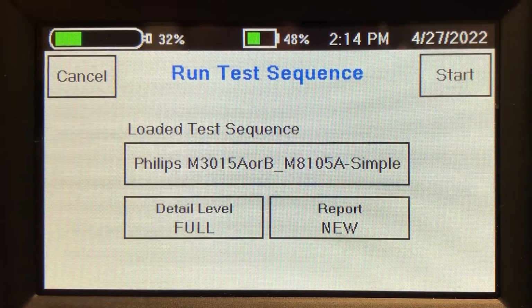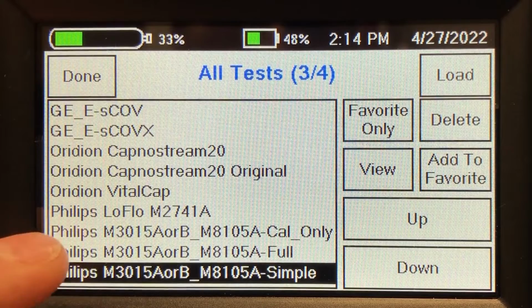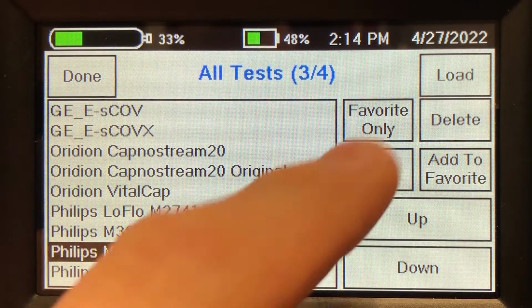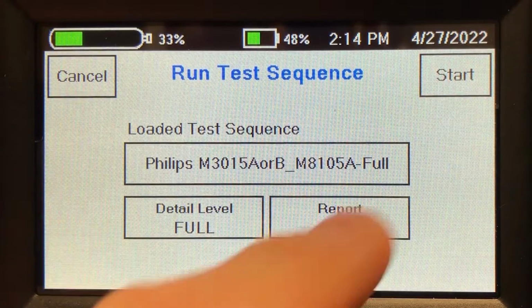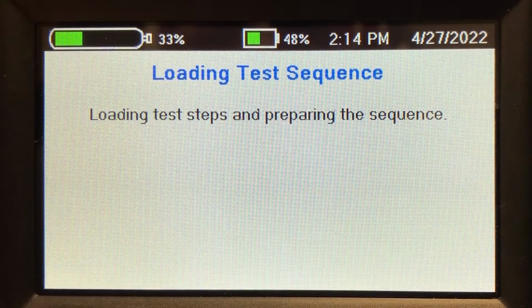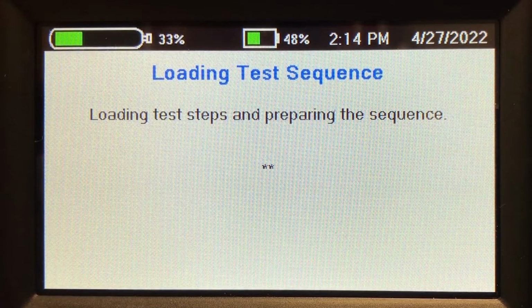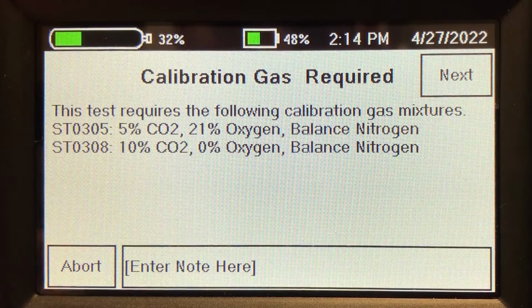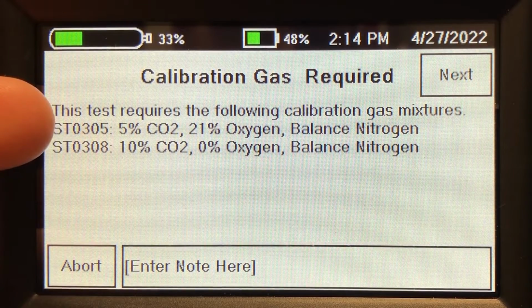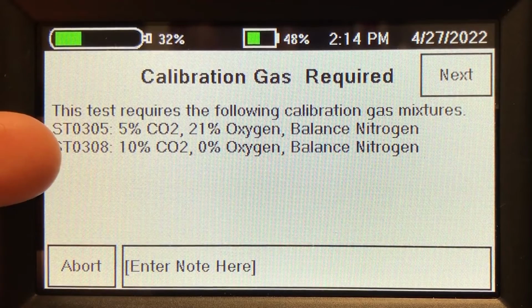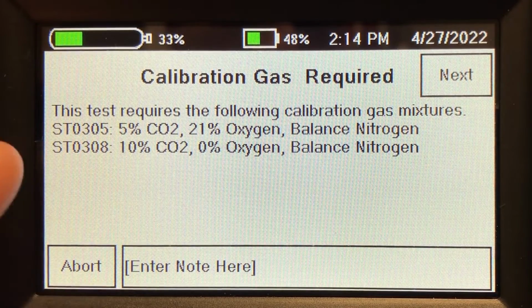Okay, I'm going to show you how to do the full manufacturer's test routine. Now, this is kind of a time-consuming test routine because their method for testing for leaks is cumbersome. So we recommend you try out the simple version. The manufacturer calls for a 5% CO2 to calibrate and then a 10% to test the span gas.